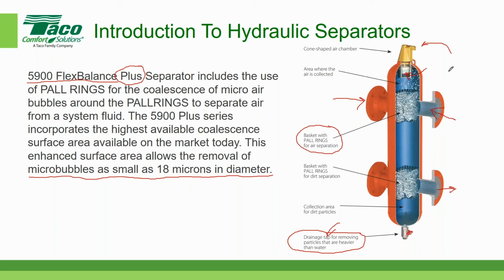Any questions about the 5900 Flex Balance Plus? Nope. I do want to add though that one of the handouts is a test, the test data for this and shows how efficient it is. Actually, there is a question. Does it have to be installed vertically? Yes, because you have to have the air vent at the top. And that's both the 5900 Flex Balance and the Flex Balance Plus. They both have air vents at the top. So they do have to be mounted vertically. Okay.